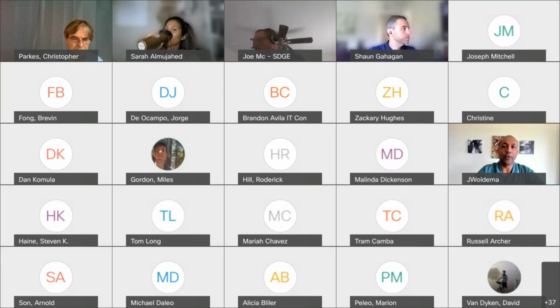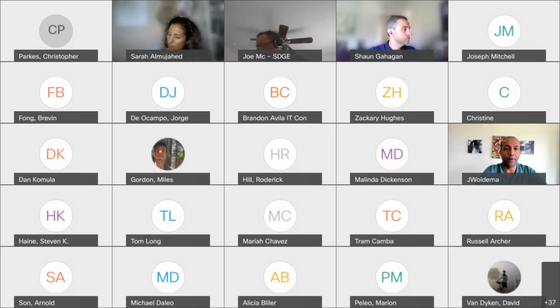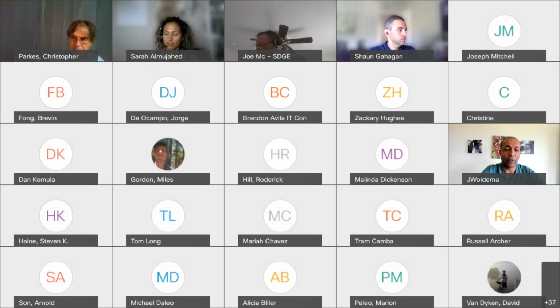Sure. So the other techniques include early fault detection, which we've implemented on one circuit so far and are continuing to expand. This looks at frayed wires, as mentioned earlier, or a tree limb sitting on a wire—intermittent issues that aren't a hard fault. We're looking at early failures showing some signs or signatures of fault, trying to catch those early. That's a technology we're deploying.